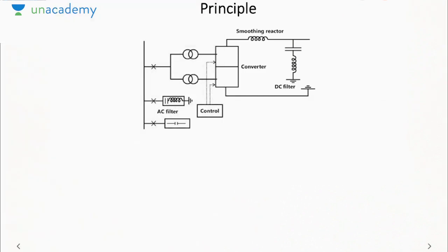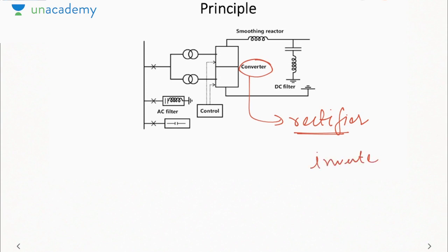Now let us look at the principle of operation of an HVDC system. In case of HVDC transmission, the generation is actually in terms of AC, because for generation we mostly use synchronous generators or three-phase synchronous generators. So before transmitting the power, we need to convert it to DC. That is why we will use a converter, which will actually be a rectifier. It will convert AC into DC before the transmission. A similar converter we will have at the receiving end, which will be an inverter. It will convert the received DC power into AC power for utilization. So here we need two converters, one at the sending end and the other at the receiving end.